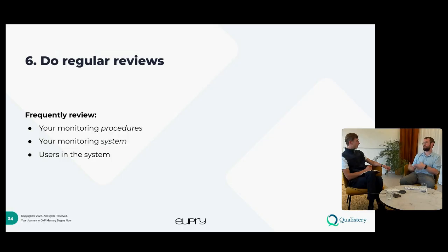So through a review process, you should also really consider your processes. Do you log on from a central computer? Do you log on from your personal computer? Where do you leave those? There are several different aspects, and I think there's often a light going on, a bright epiphany. When you tell them that you could easily do a legally binding signature in a 21 CFR Part 11 compliance system if you have the user, people start to think much more about how to protect their passwords and their login credentials. That's a very important thing to remember, I think.